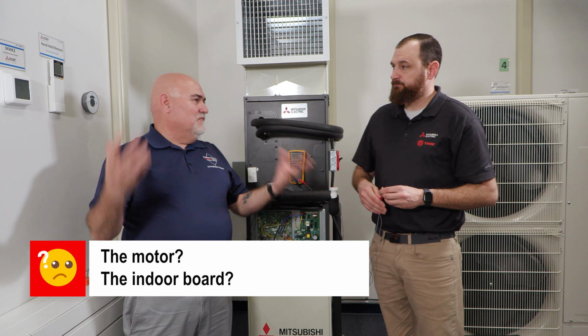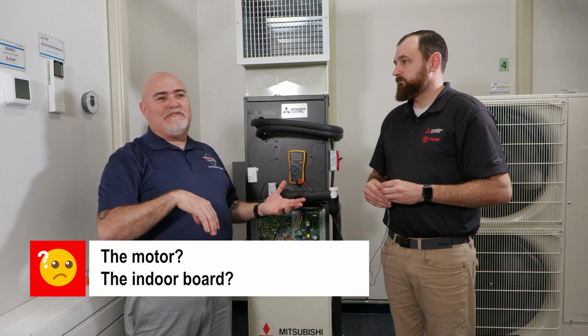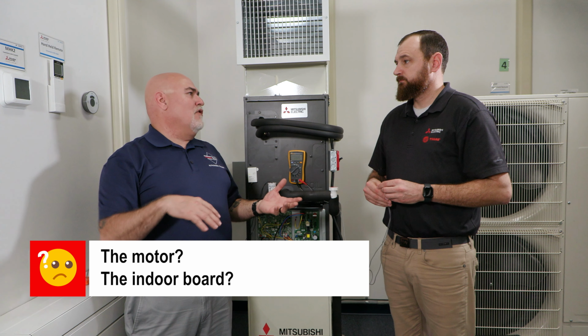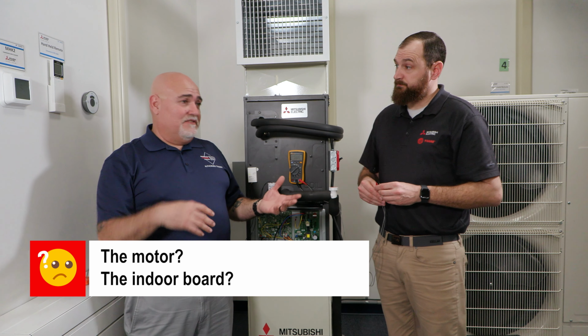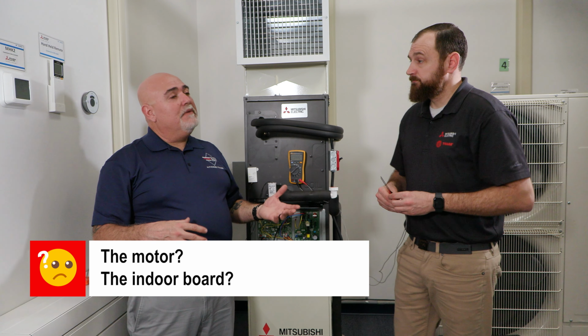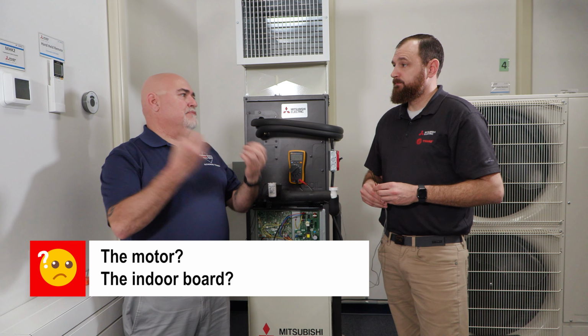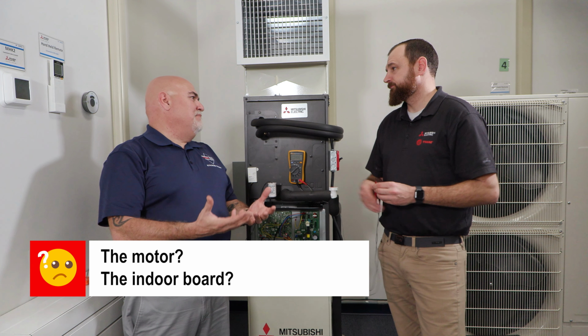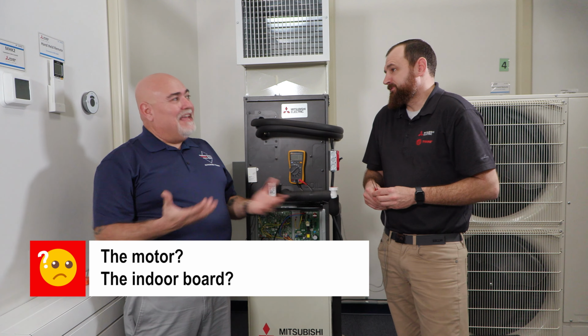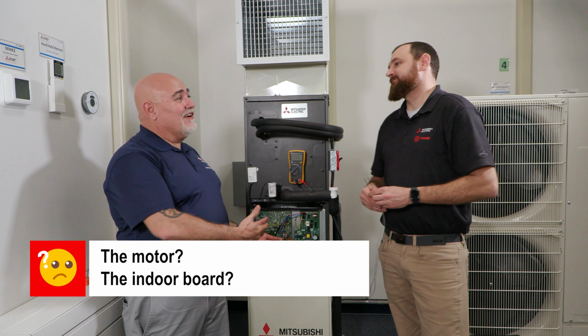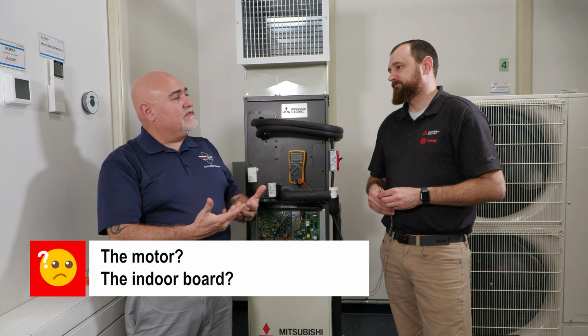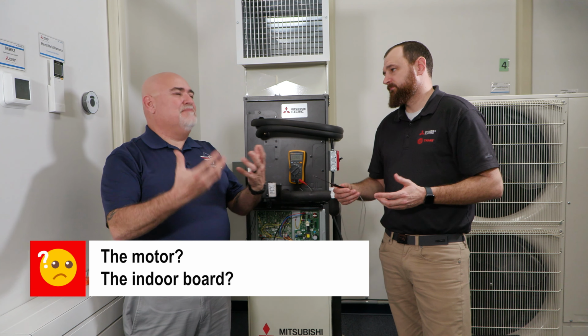Okay. Now, we get a ton of boards back to the factory every year that have nothing wrong with them. We get a lot of motors back to the factory every year with nothing wrong with them. And it's common practice for a lot of technicians out in the field to change both. They change out both. Now, why are they changing both? They're not going through all of this work, right? Exactly. And they don't want to come back to that customer's house for a second or third time to replace a component because it was misdiagnosed.